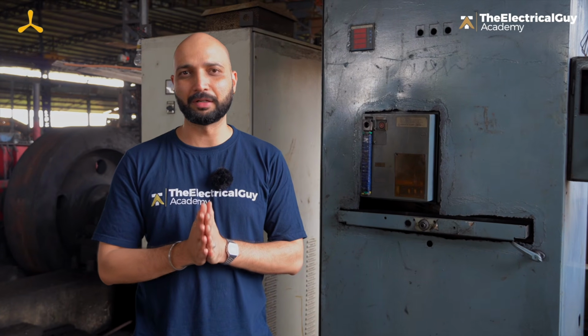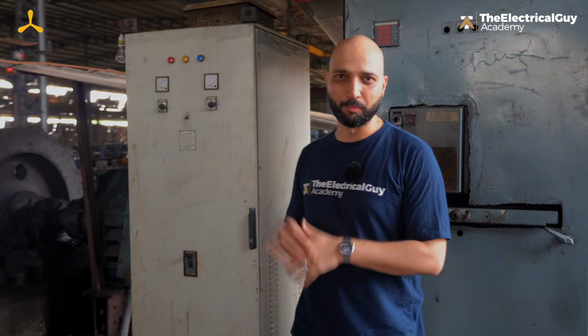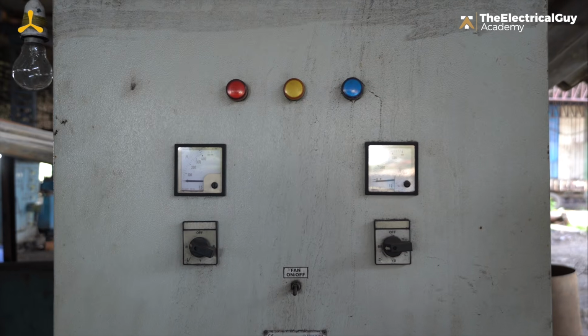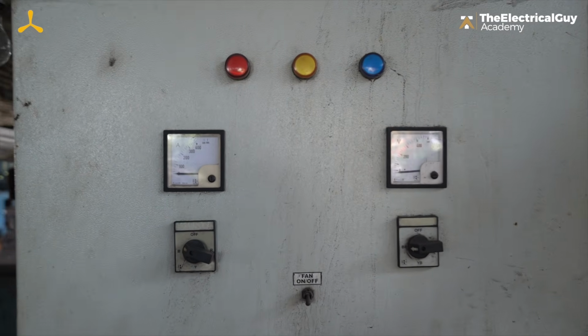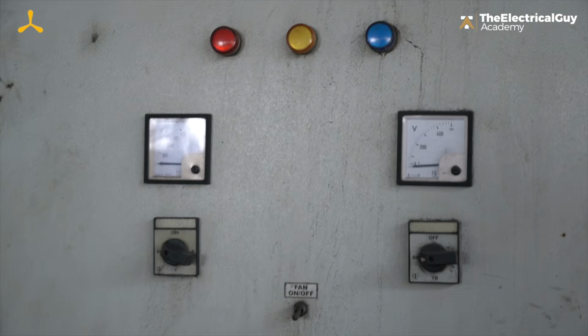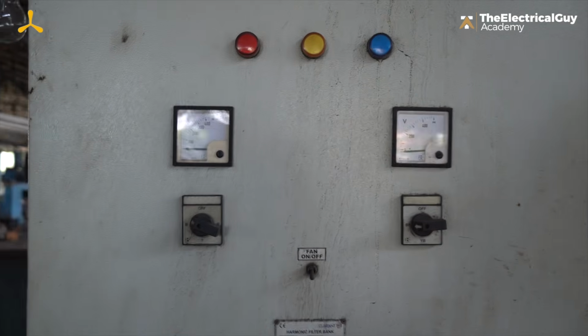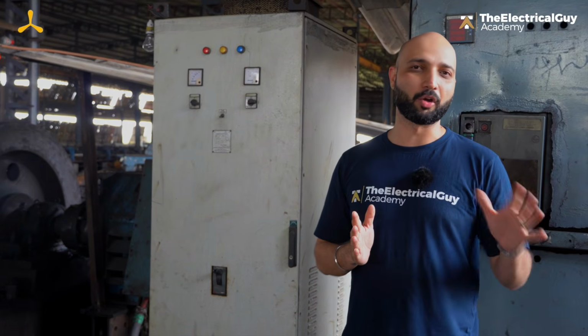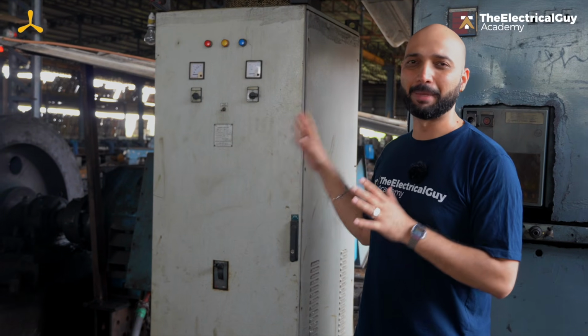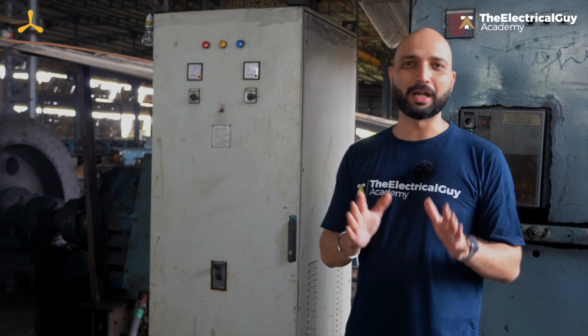Now we have talked in detail about the power factor in the power factor series. Now let me show you the automatic power factor correction panel that is specifically given for this motor. So you can see here, this is the automatic power factor correction and also the harmonic filter bank. This will help make sure the motor does not consume huge amount of electricity. Otherwise, the electricity bill will skyrocket. So this panel helps in maintaining a better power factor so that the electricity bill stays in control. And of course, the motor's life is also better.